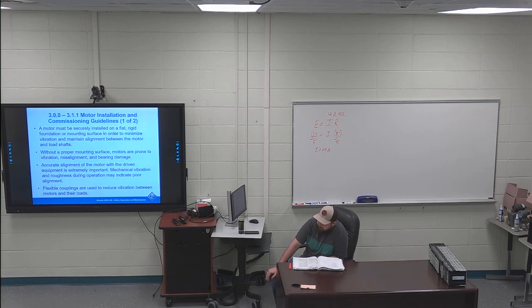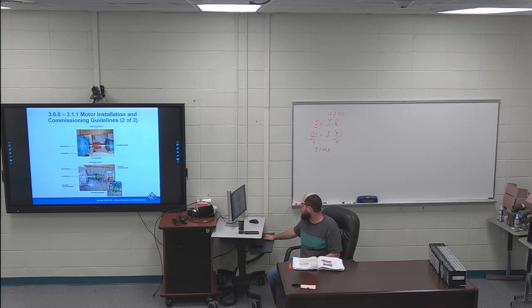312, end play adjustment. That's like what I talked about when the shaft moves in and out. Like, you want some of that. But if you are wanting to adjust the end play, then the highlight I have is the second to last sentence on page 25. Shim or reposition, and then tighten the bearings as necessary for adjusting the end play. And you see the couple different types of couplings on the next page or up here on the board. You've got the Lovejoy coupling, which is what you use in the lab here if you do the braking lab on the motor trainer, and then you can have the spline coupling down here.